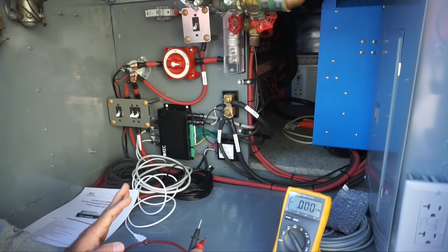We do. So across cell 1, 3.97; cell 2, 3.97; cell 3, 3.97; cell 4, 3.97; cell 5, 3.97; cell 6, 3.97; cell 7, 3.95; cell 8, 3.95; cell 9, 3.97; cell 10, 3.97; cell 11, 3.97; cell 12, 3.97; cell 13, 3.97; and finally cell 14, 3.97. So we've got the proper voltages coming in.